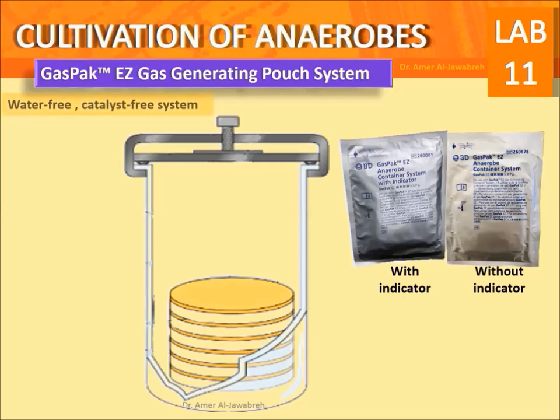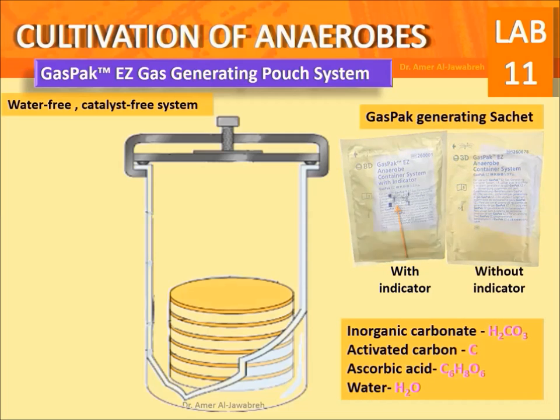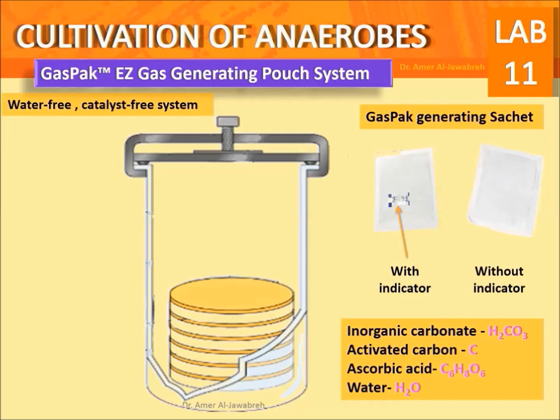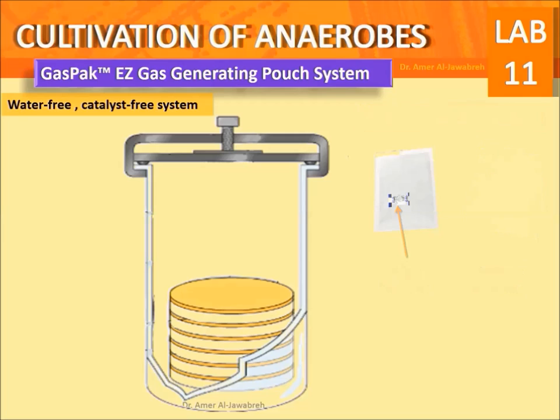GasPak EZ gas generating pouch system: a water-free, catalyst-free system. The GasPak generating sachet comes with or without an indicator. The sachet contains inorganic carbonate, activated carbon, ascorbic acid, and water. Air activation starts as soon as the foil wrap is removed; put it into the jar within one minute. If a sachet without indicator is used, an indicator should be placed along with it.